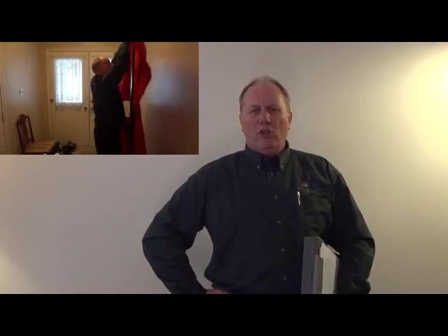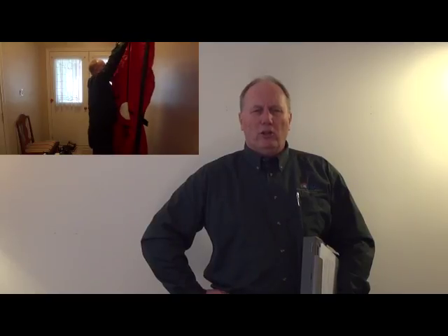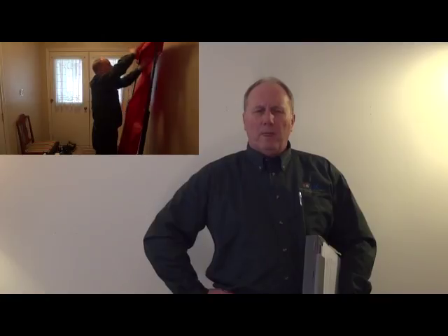Okay, we're going to begin the blower door test by installing the blower door, which is a large frame that goes in an exterior door. It consists of a large fan with multiple rings so that we can control the amount of air that's flowing in or out of the building. It's controlled by a manometer. The manometer is connected up to the blower door, and it's also connected up to a tablet computer that controls the flow that's happening between the inside and the outside of the home.